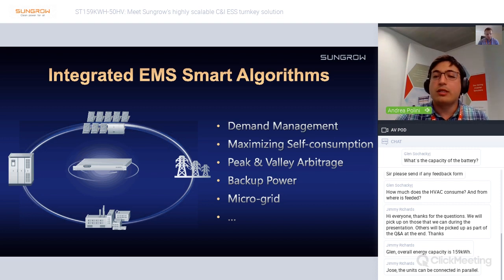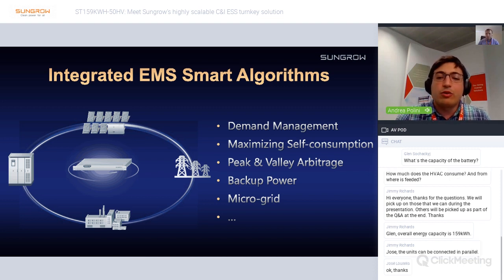So the local controller has a simple integration with the customer EMS system. In fact, it has a Modbus TCP protocol, and using that, the client EMS system can get all the data and all the measurements from the local controller, and also send commands like charge and discharge from the battery to control the full system. In addition to this, the local controller is the brain of the ESS product, and it has several smart EMS modes already built in. So for example, self-consumption maximization mode uses data from the existing PV inverter plant.